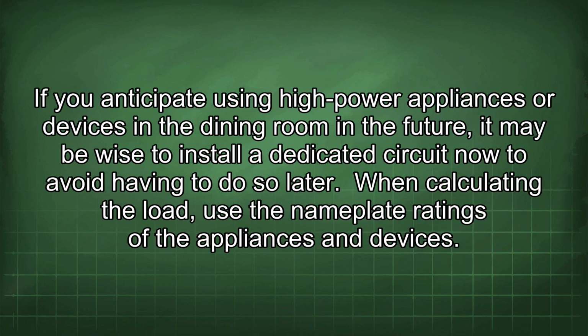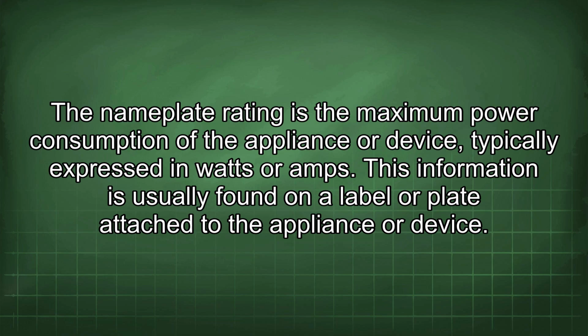Consider the potential future use of the dining room receptacles when determining whether to install a dedicated circuit. If you anticipate using high-power appliances or devices in the dining room in the future, it may be wise to install a dedicated circuit now to avoid having to do so later. When calculating the load, use the nameplate ratings of the appliances and devices. The nameplate rating is the maximum power consumption of the appliance or device, typically expressed in watts or amps.